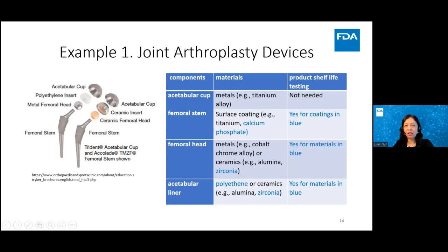FDA has issued a guidance on this material in 2019. Here are some images of this specific acetabular insert. This guidance recommends that, since the mechanical properties of polyethylene that contains unstable free radicals may degrade if the product is exposed to air during shelf storage. In addition, the shelf life of this material that has been irradiated and packaged in an inert environment may be limited by the integrity of the packaging material. Therefore, we recommend the stability of this material be assessed for the duration of its specified shelf life.